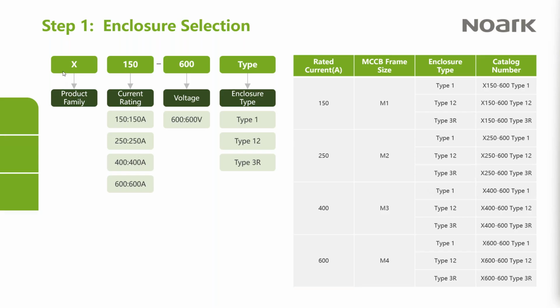And what you'll see here is the same kind of thing. It's X. 150 is the frame rating of the breaker that it's designed for. The 600 volts is always the same because we have a 600 volt rating on them all. And then the enclosure type. As you can see here to the right, it's pretty straightforward. An M1 type 1 is an X150 600 type 1. Okay.